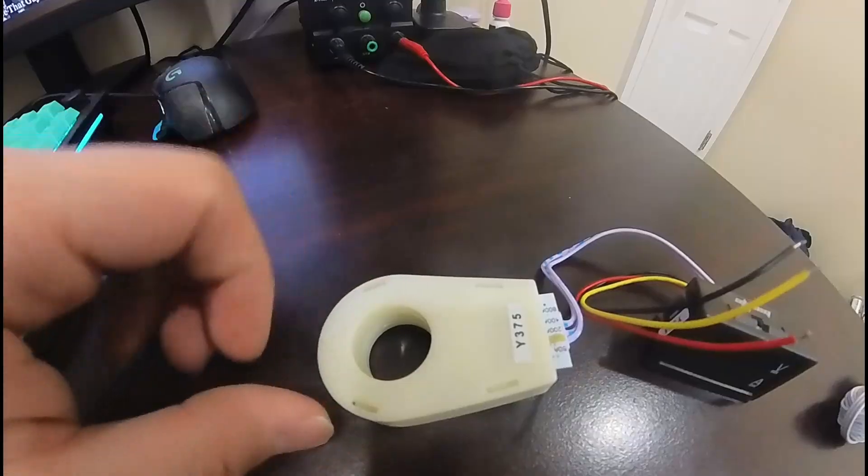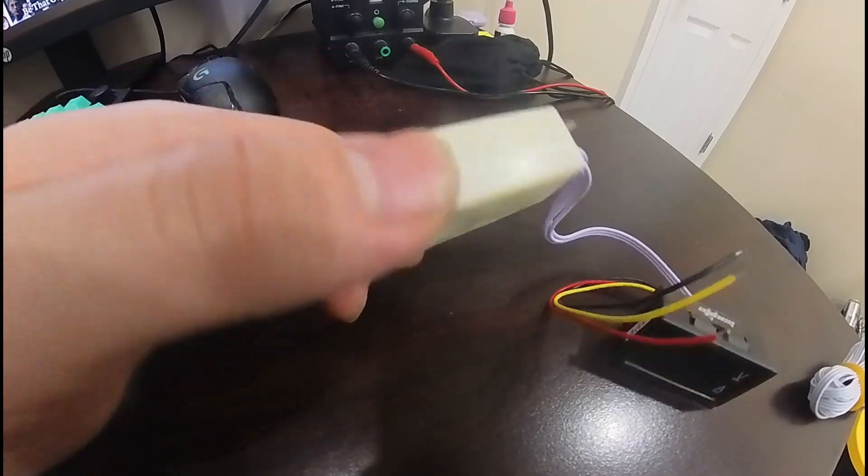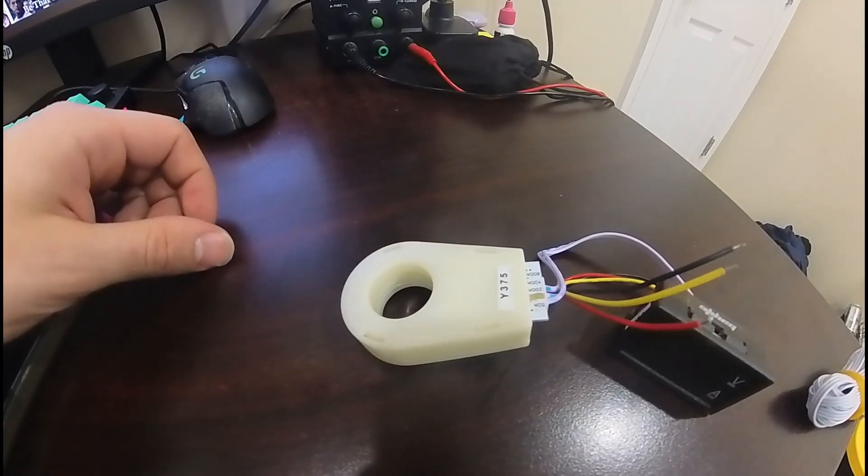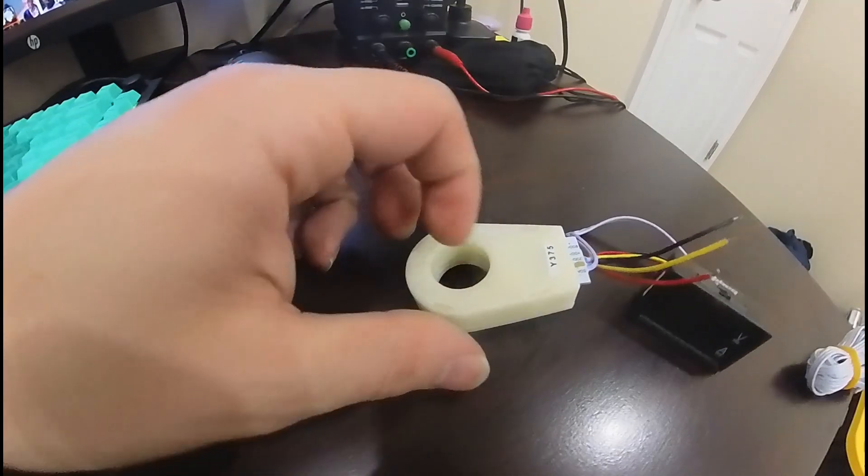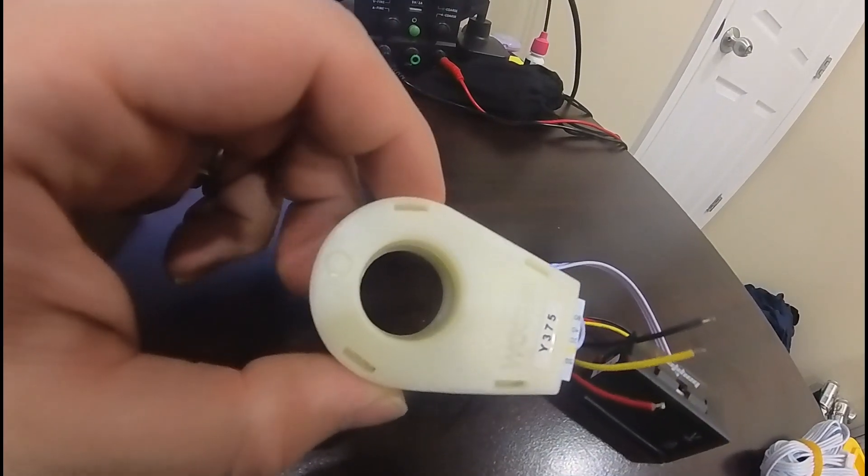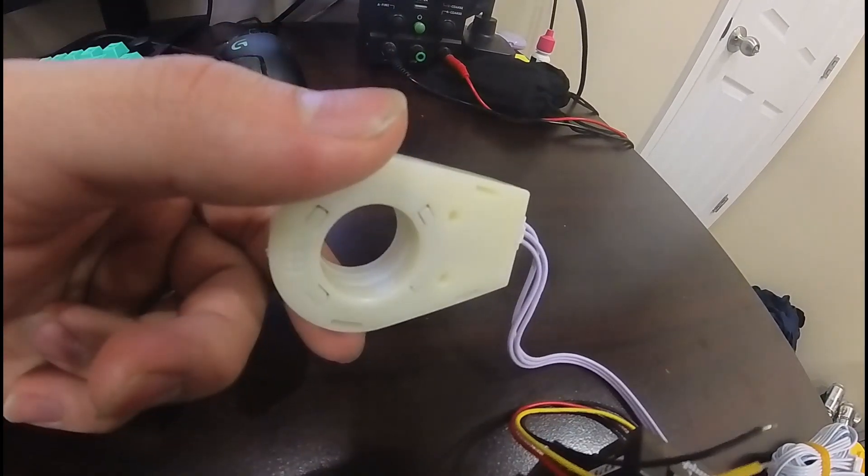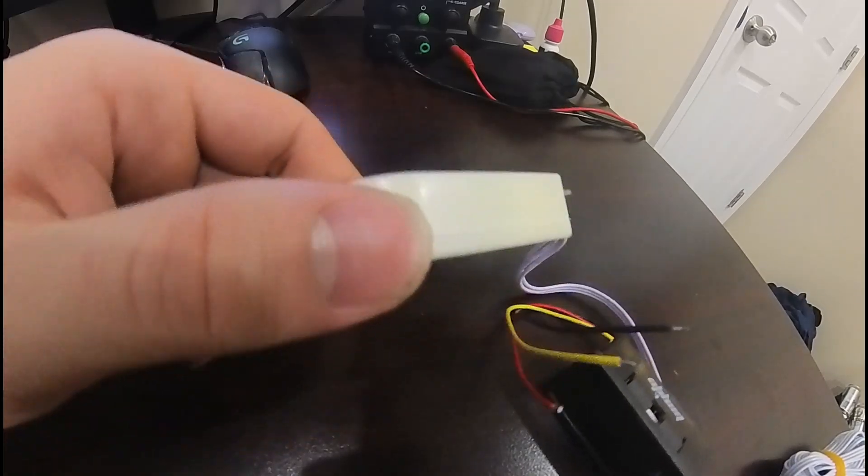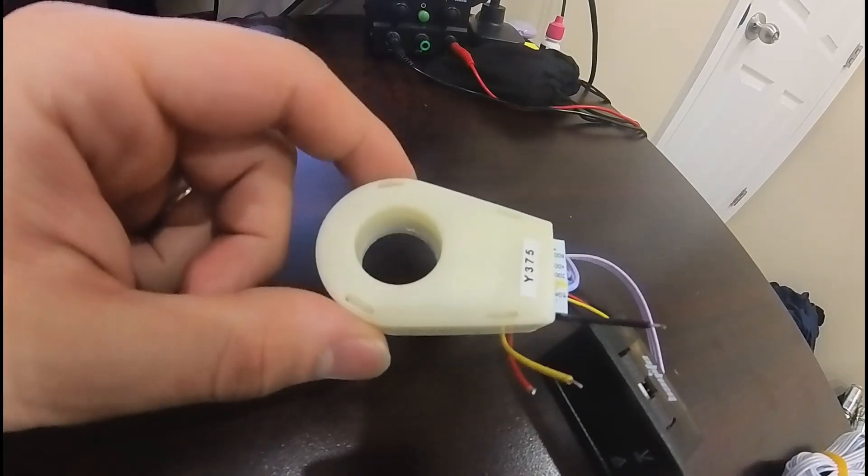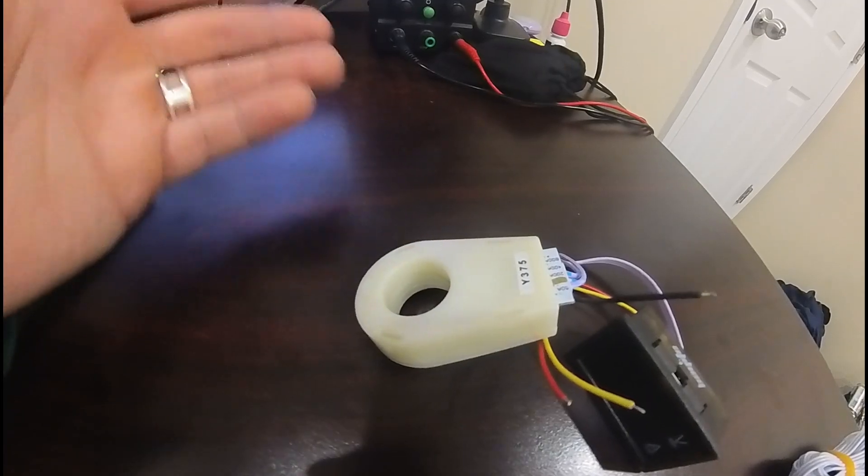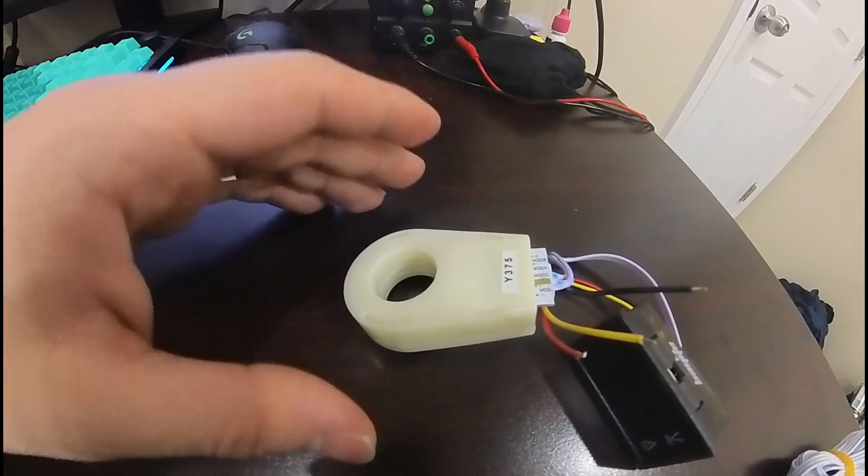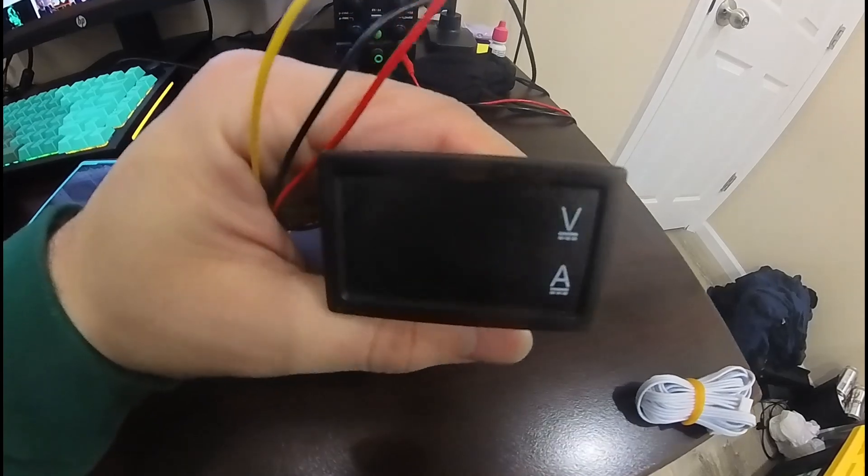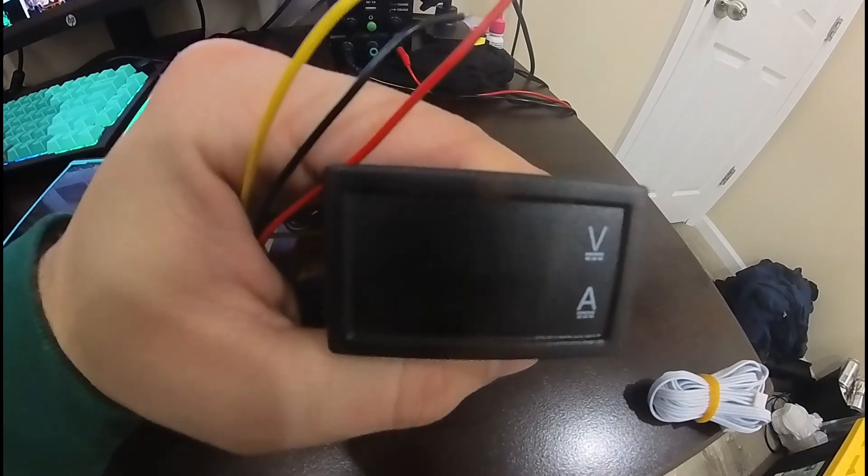This sensor here unfortunately does not come with a clamp, which means you have to wrap it around the wire before putting on the terminal. The way it works is that it uses a hall effect sensor to measure the magnetic field that the wire is creating and it can take a somewhat accurate measurement of the amps. It's not super accurate, but when you're dealing with 50 to 100 amps, this has enough accuracy.